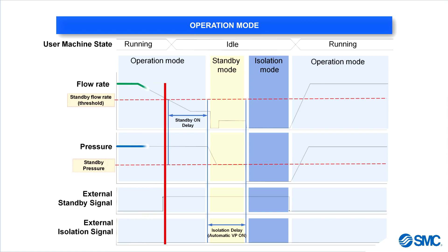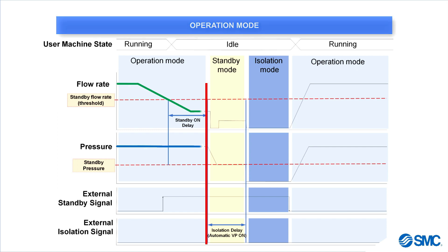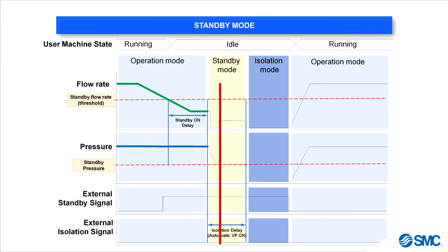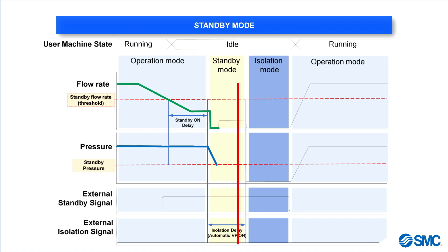When the user machine goes into idle mode, the flow rate drops. Once the flow rate drops below the standby flow rate threshold, the standby on delay timer is started. After the standby on delay time period has passed, if the standby input signal is still on, the system will lower the standby pressure.